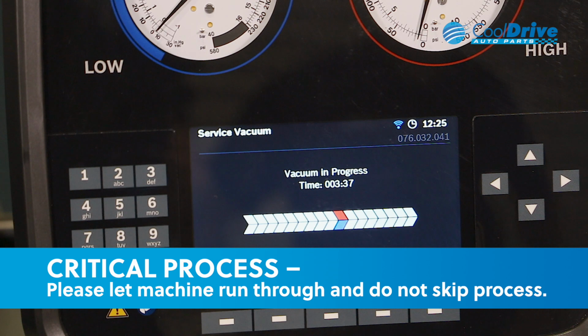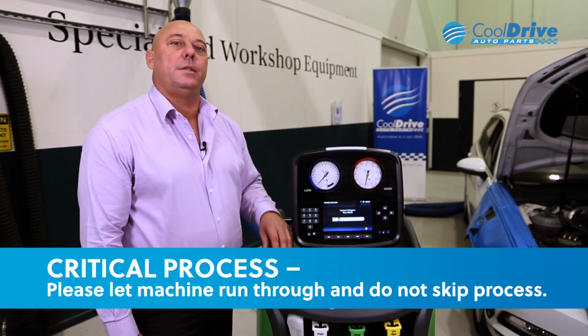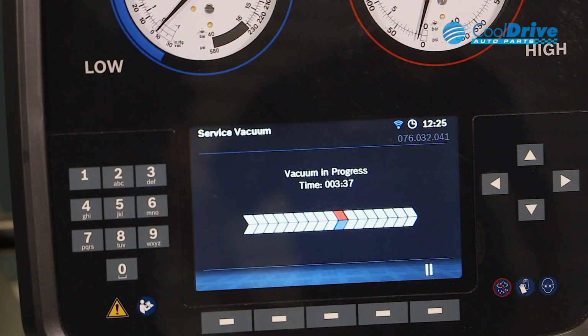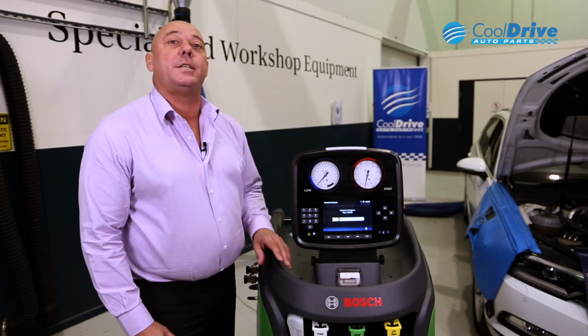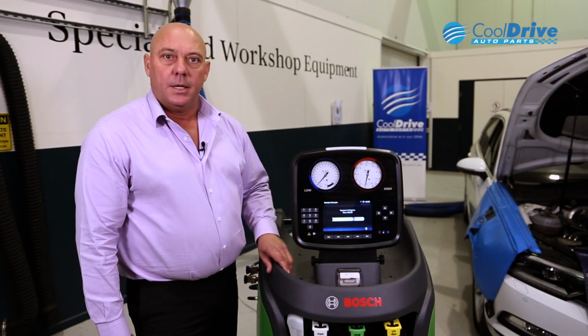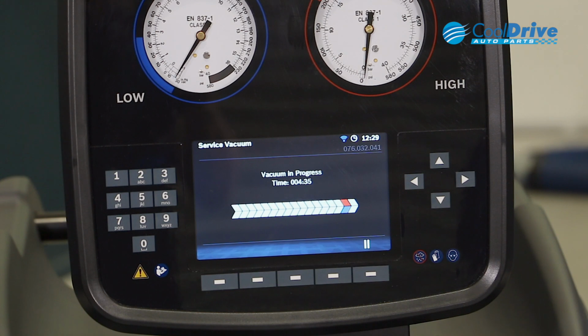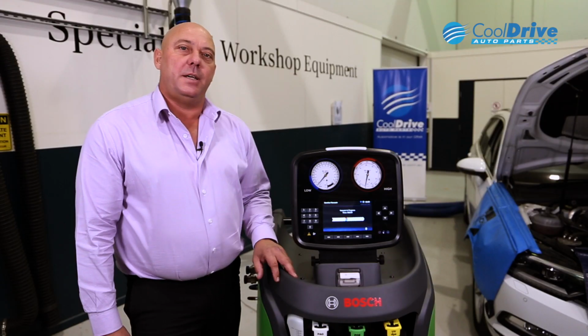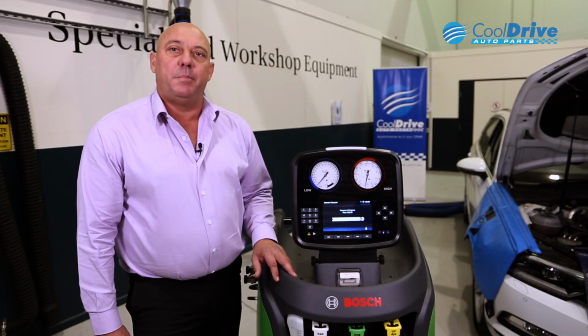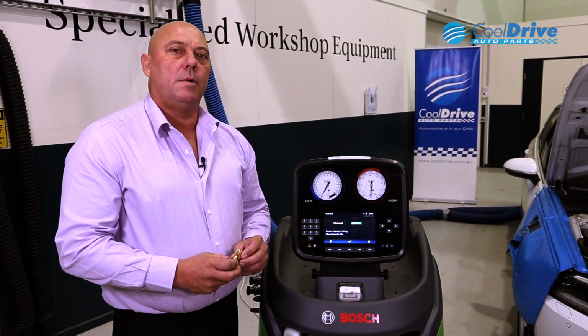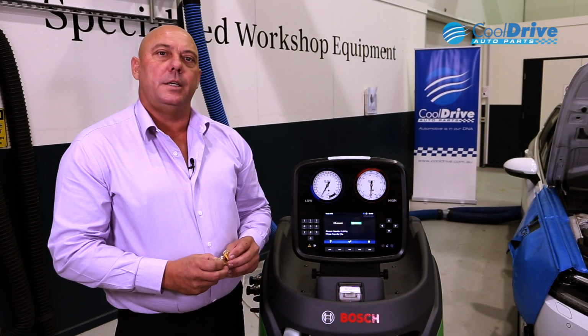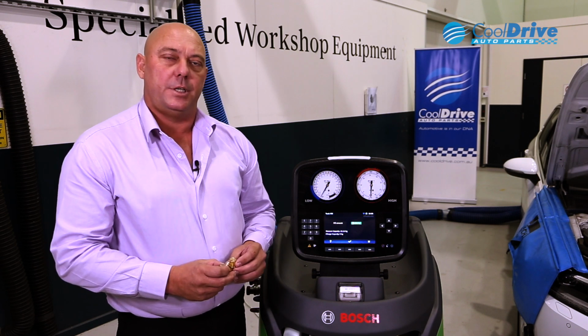It's of most importance we let this process complete itself rather than just pausing halfway through. This actually flushes the machine and sets it up ready for a tank filling process. Approximately 5 minutes. This step actually vacuums itself out internally in preparation for tank filling. Once the service vacuum is completed, it's time to actually add refrigerant to the machine itself.